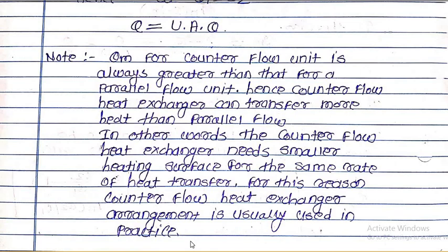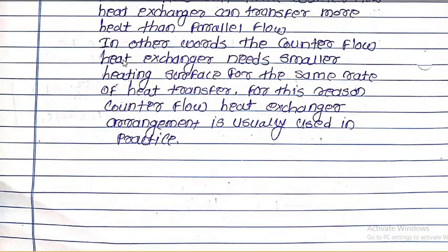So theta m, the logarithmic mean temperature difference for a counter flow heat exchanger, is always greater than the logarithmic mean temperature difference for a parallel flow case. For that reason, in practice the counter flow heat exchanger is always used.